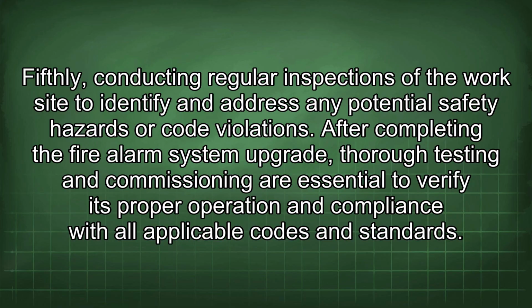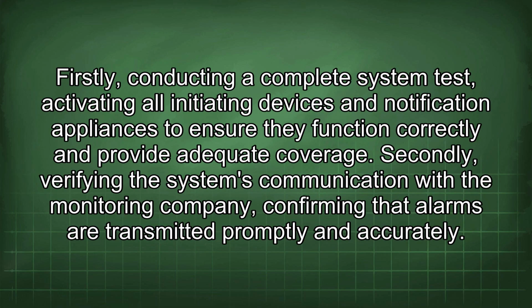After completing the fire alarm system upgrade, thorough testing and commissioning are essential to verify its proper operation and compliance with all applicable codes and standards. Firstly, conducting a complete system test, activating all initiating devices and notification appliances to ensure they function correctly and provide adequate coverage. Secondly, verifying the system's communication with the monitoring company, confirming that alarms are transmitted promptly and accurately.